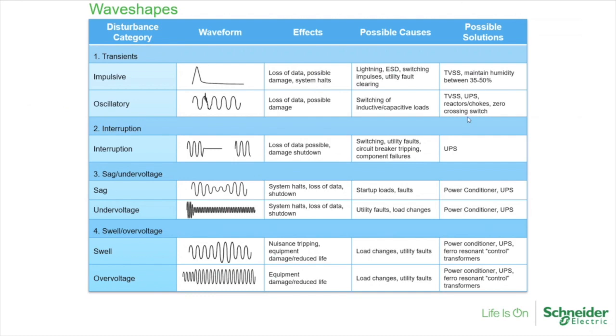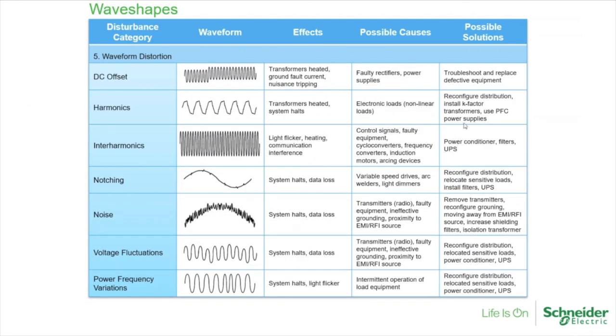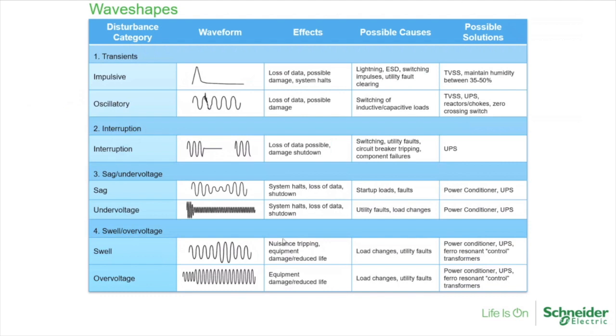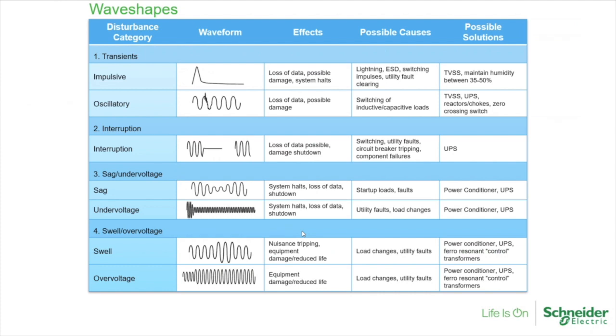Gotcha. Thanks. And hey, Nate, Virgil Johnson wants to know, there seems to always be a certain amount of transients we measure. At what point should we be worried about the transient? I think when you're looking at transients, probably frequency, especially if your transient voltages are exceeding your voltage ratings. You're hitting your equipment with a lot of voltage, and if it's happening all the time, you're going to reduce the life of that equipment. And then also identifying where the cause is coming from.